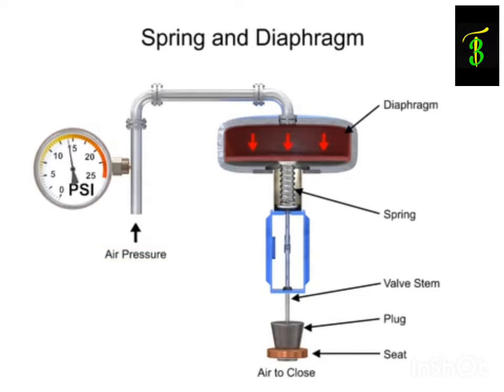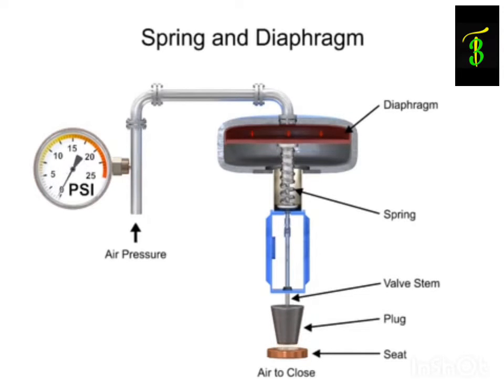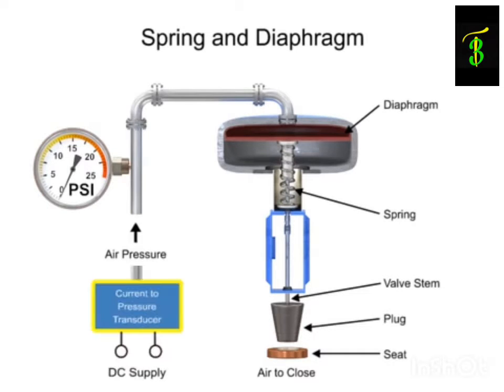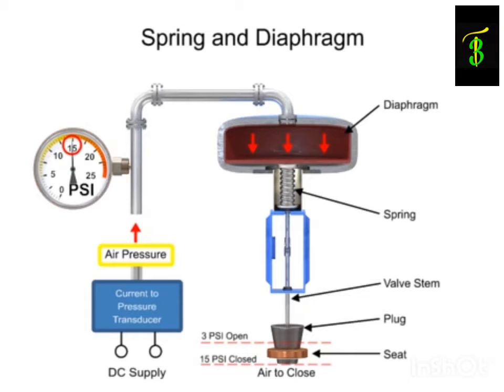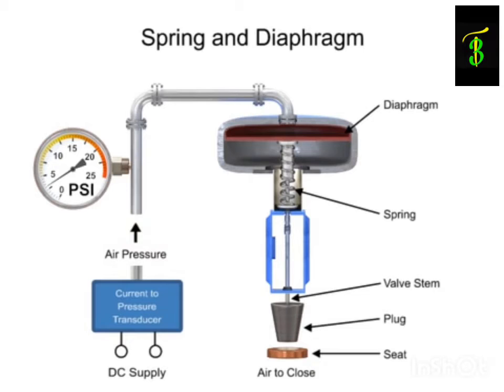With no air pressure, the restrictor is pushed upward by the spring to act as a normally open control valve. To vary the position of the restrictor and flow through the valve, a current to pressure transducer can be used to provide a 3 to 15 psi signal to the diaphragm. At 3 psi the valve is maintained open and at 15 psi the valve is maintained closed. Pressures between the 3 to 15 psi range proportionally change the flow of the valve.